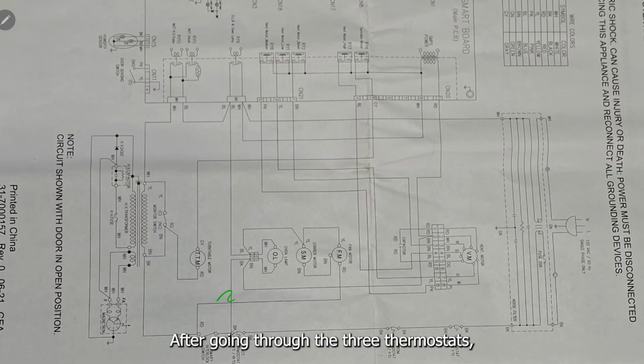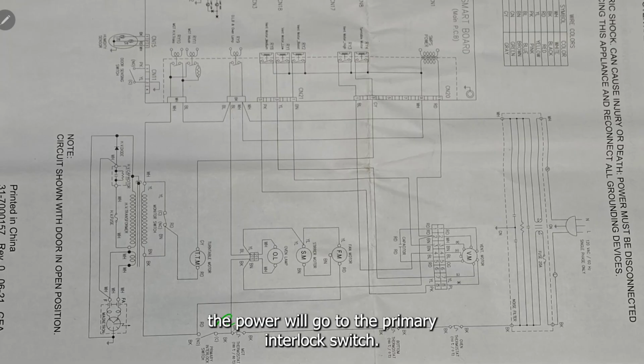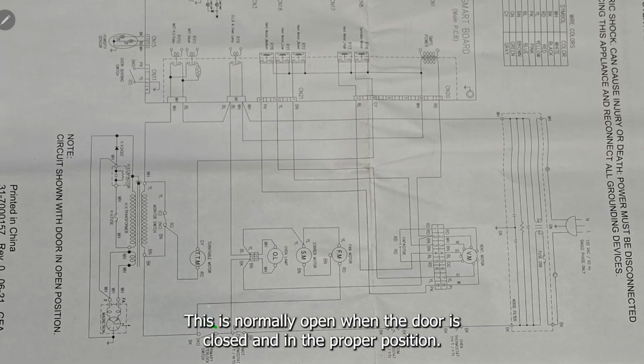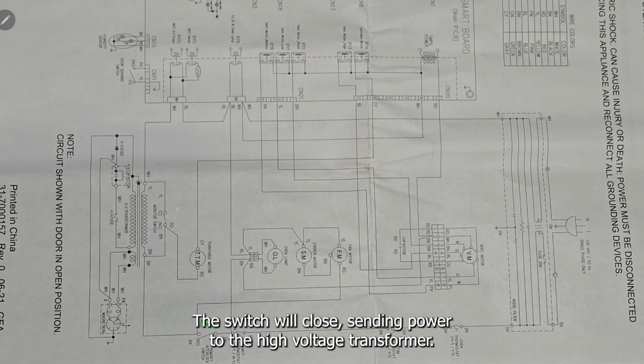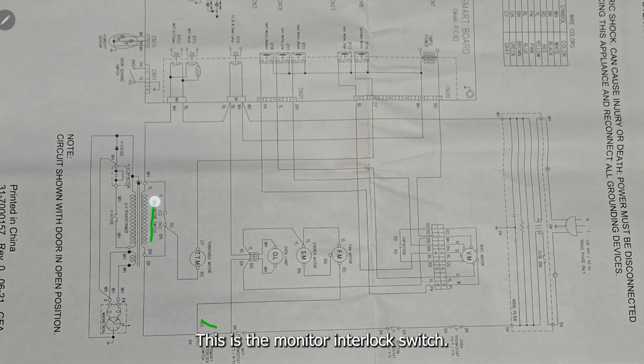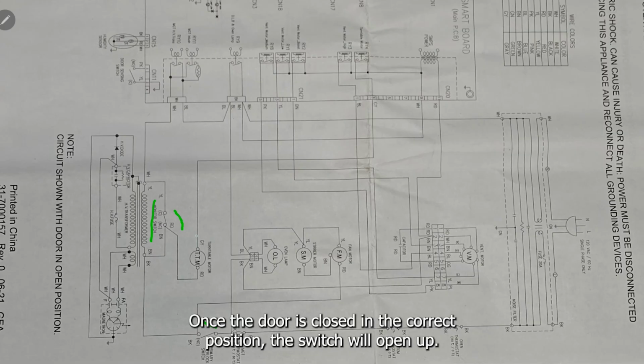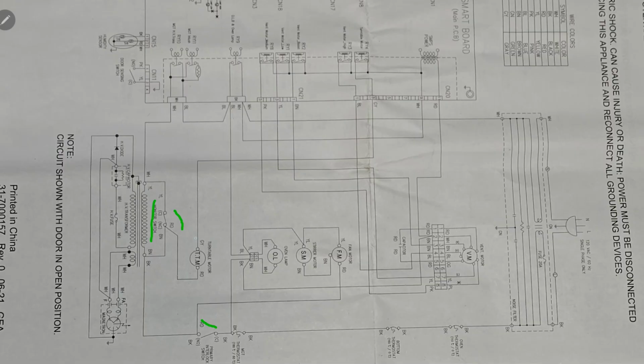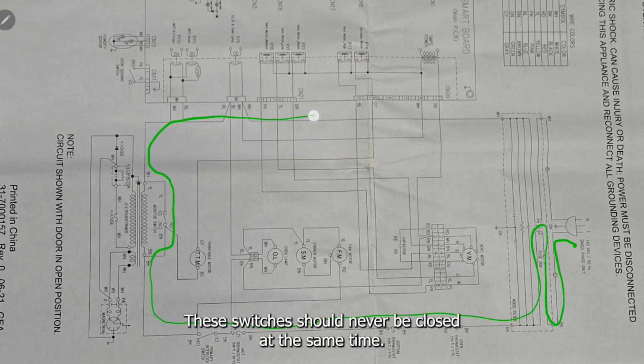After going through the three thermostats, the power will go to the primary interlock switch. This is normally open. When the door is closed and in the proper position, the switch will close, sending power to the high voltage transformer. This is the monitor interlock switch. It's normally closed. Once the door is closed in the correct position, this switch will open up. If the door is open, the main high voltage transformer is shorted. These switches should never be closed at the same time.